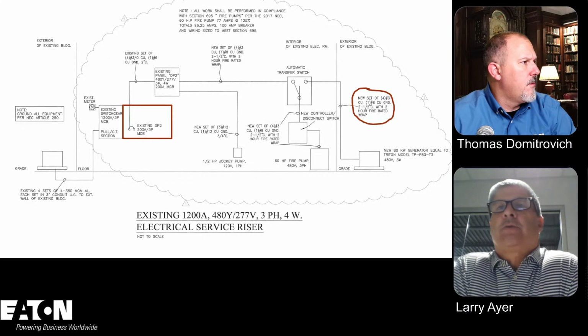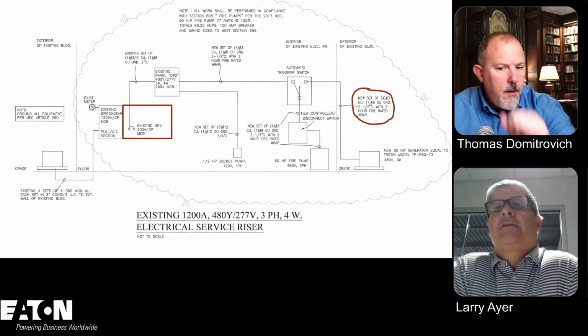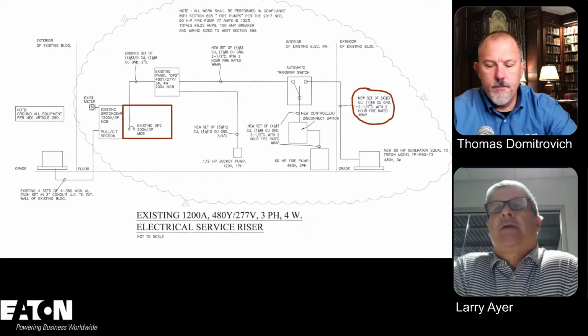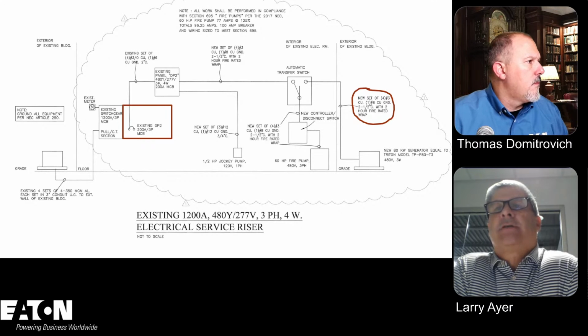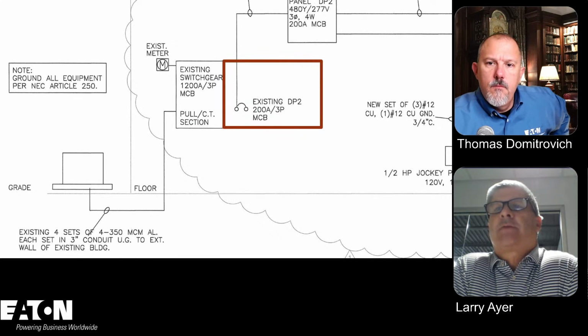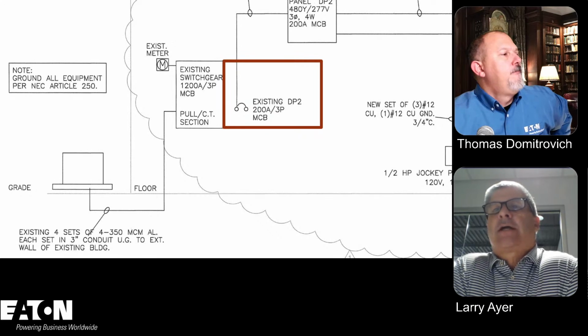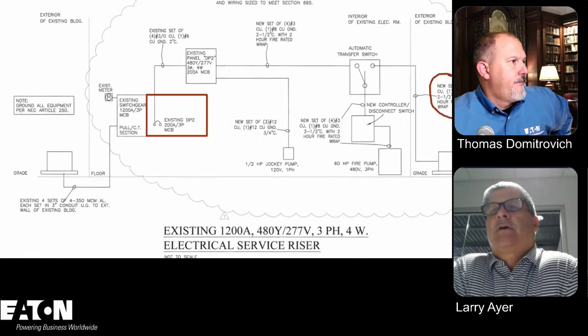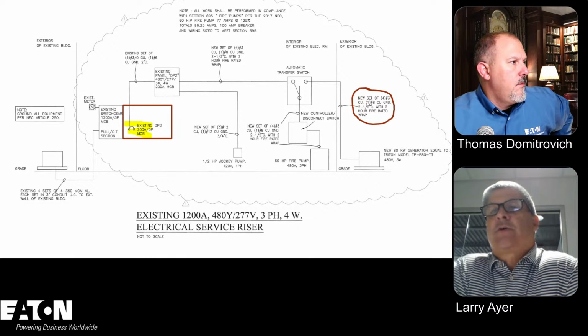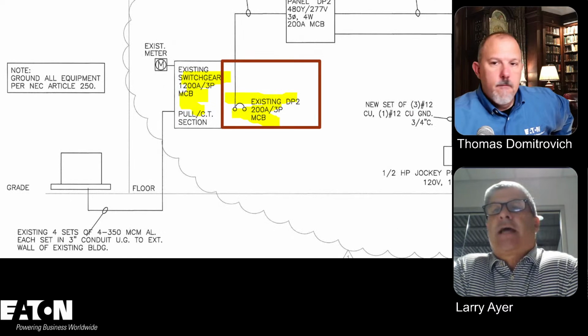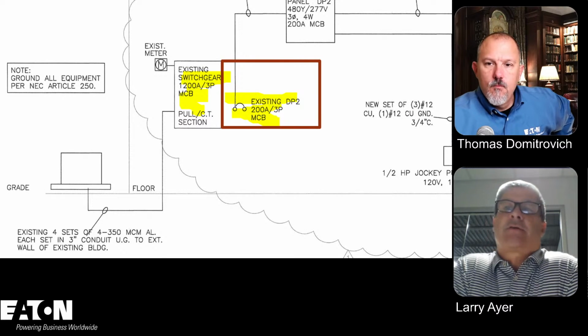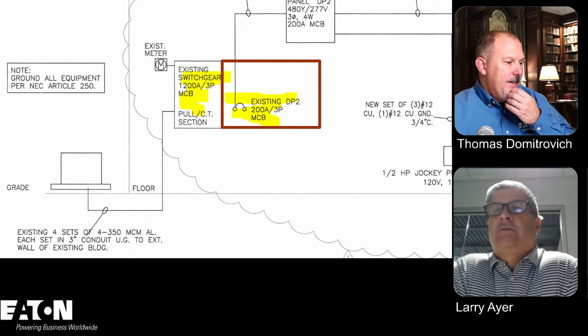So it is quite interesting. I talked to the local plan review official that had this one. They've gone through several iterations to try to fix this. So, for instance, if you look at the little red box on the left, this person was submitting these plans to put a breaker in the switchboard section, which is not a separate switchboard section. This is with all the other overcurrent devices, which you're not allowed to do. If you're going to tap off that switchboard, you have to have it separate, and not in the section where all the other overcurrent devices are. So that was one issue.